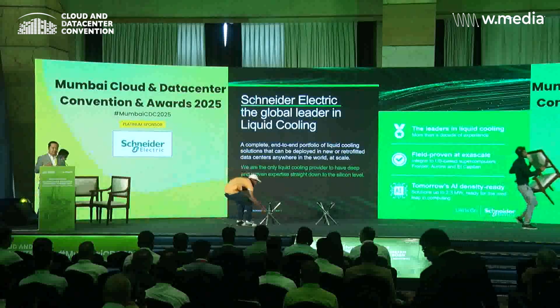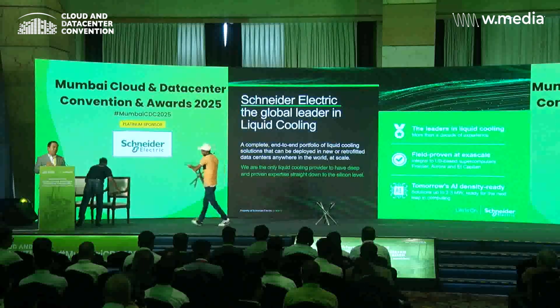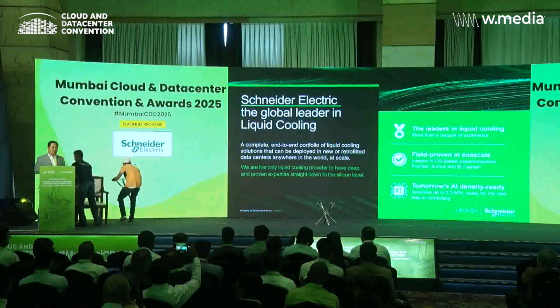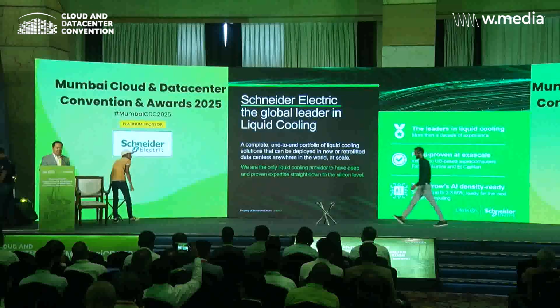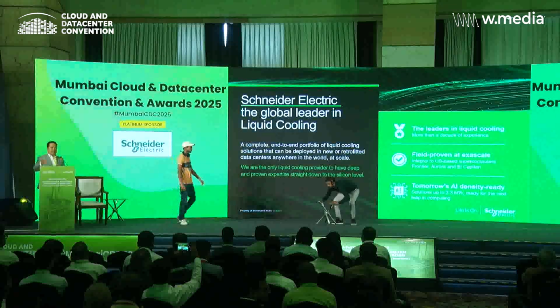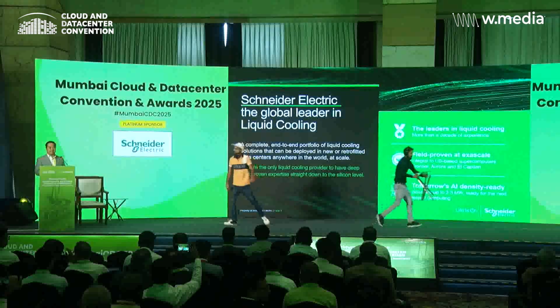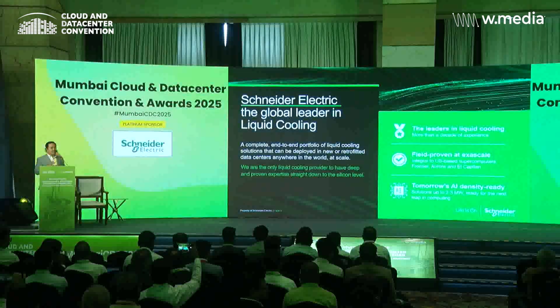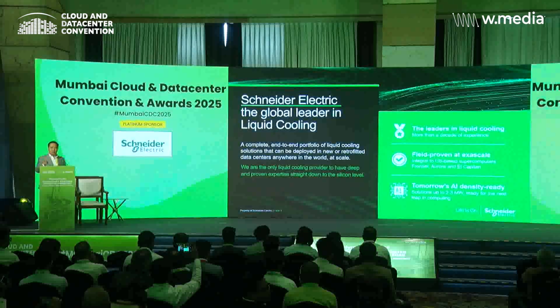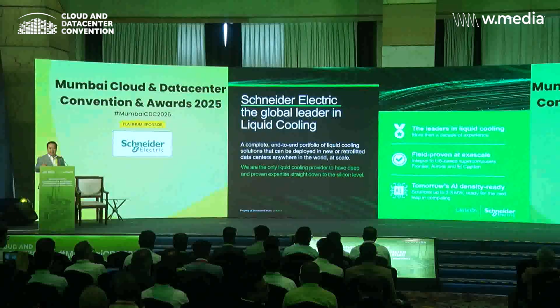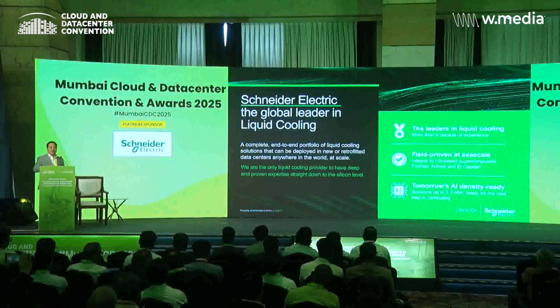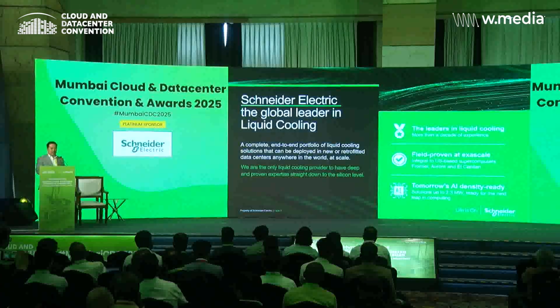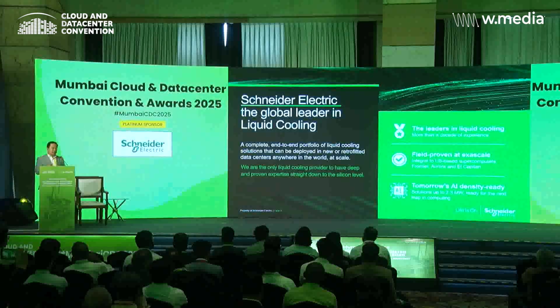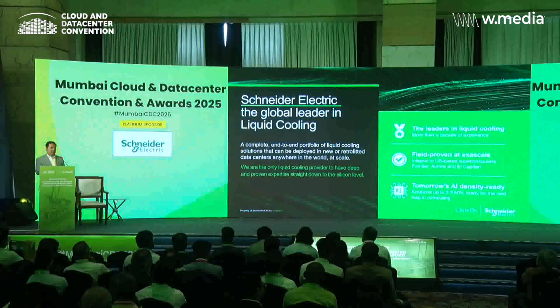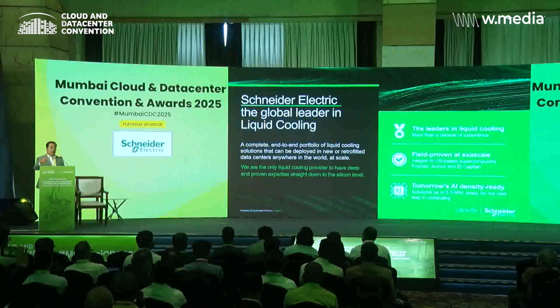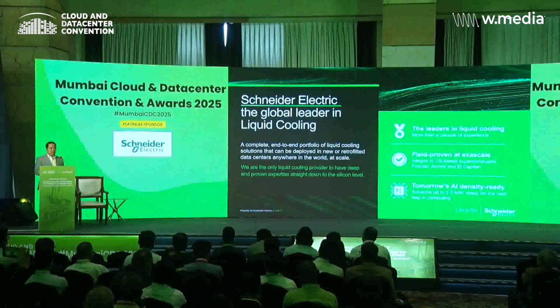We'll talk about multi-megawatt deployments of up to 400 kW per rack with liquid cooling, done 10 years ago. We're taking that application and scaling it to meet today's requirements. That means we've already cooled densities above 400 kW. Now, with AI, we have to scale that so it's available across the board to everyone. It's at 130 kW today, and we'll quickly go to 250, 400, 600, and all the way up to 1 megawatt and beyond.